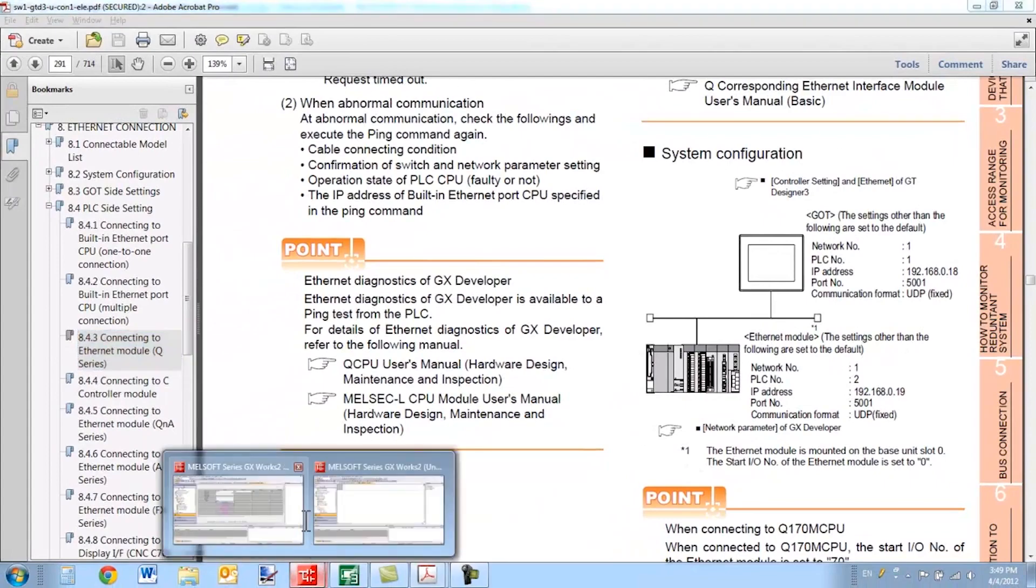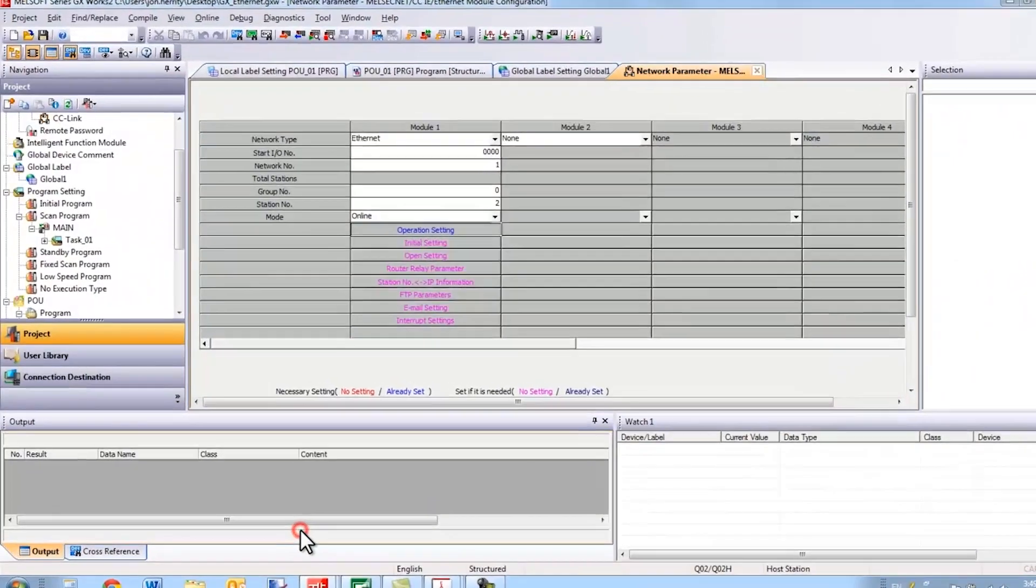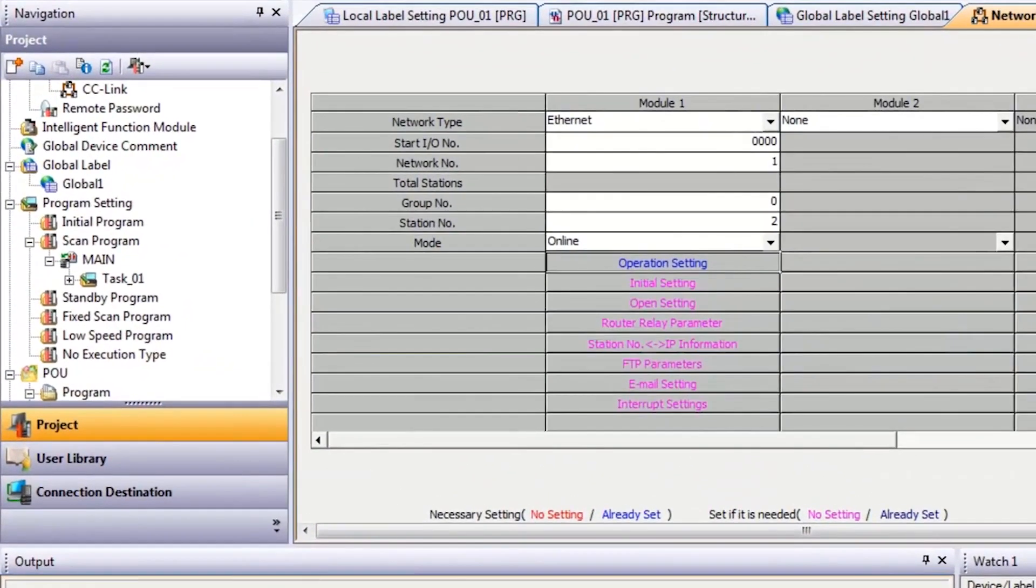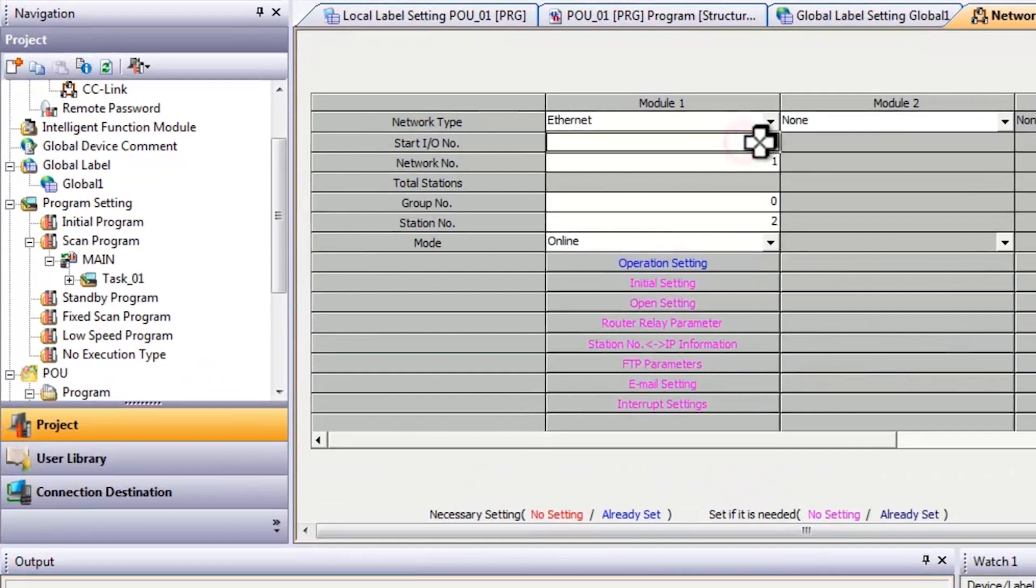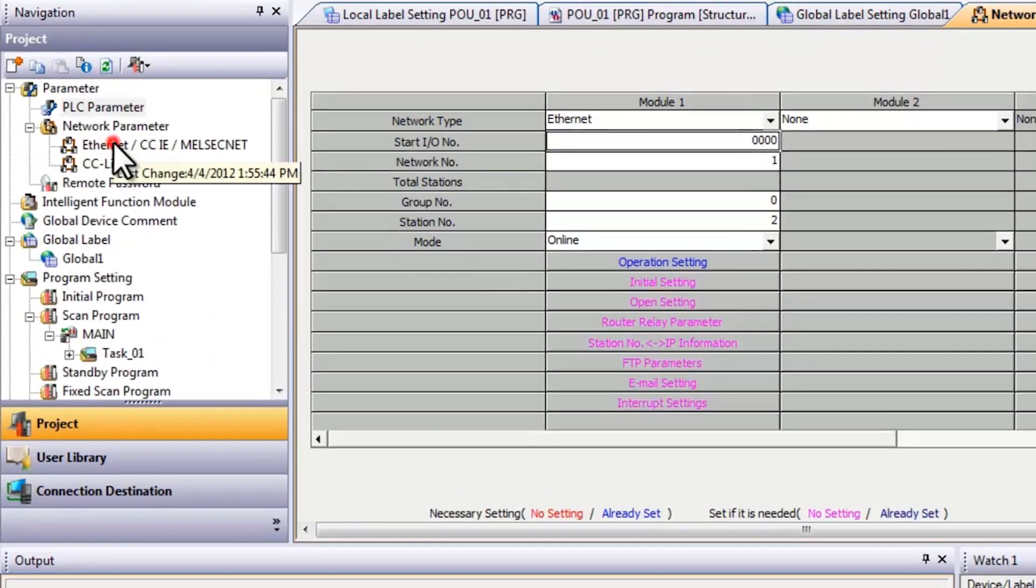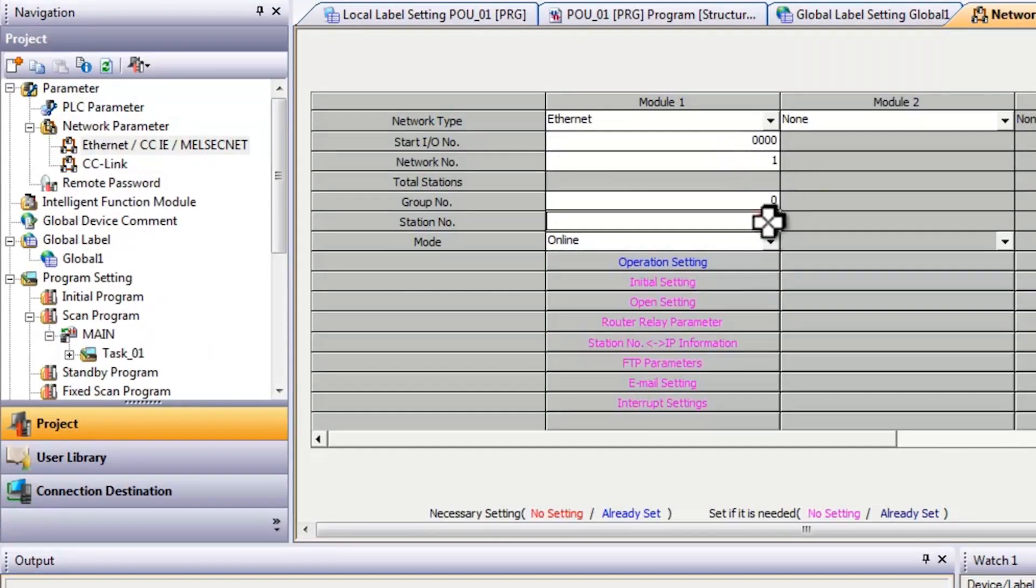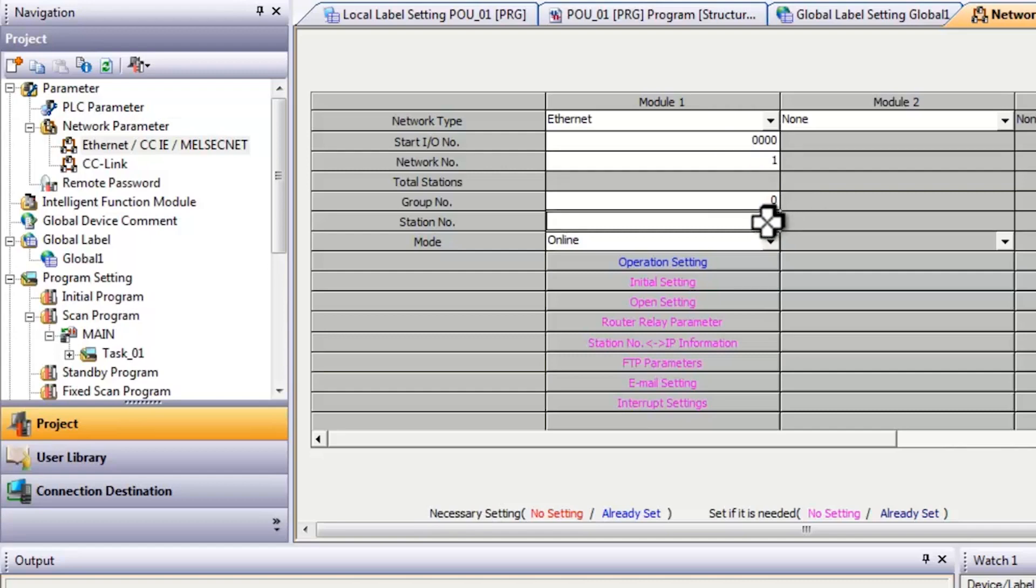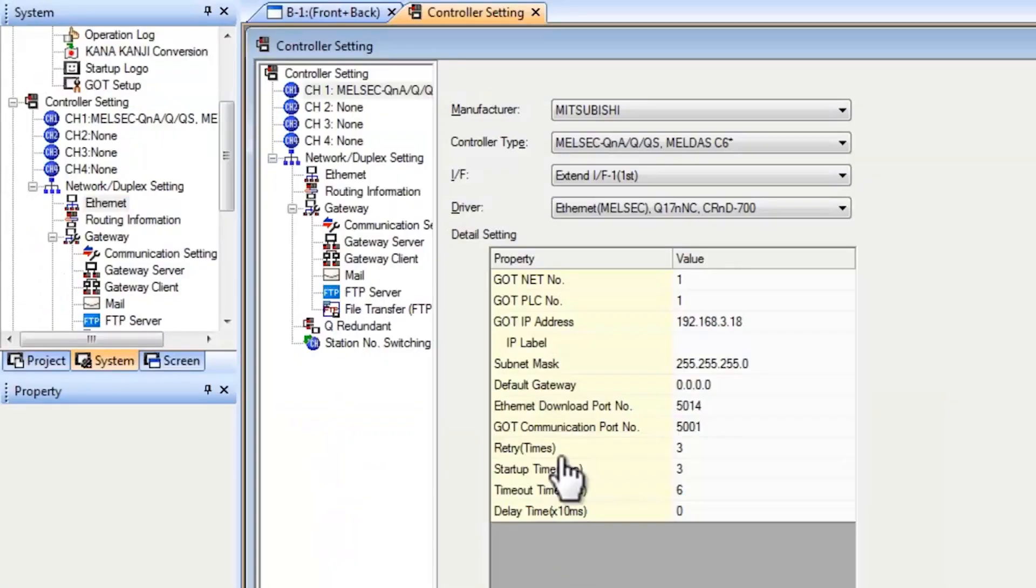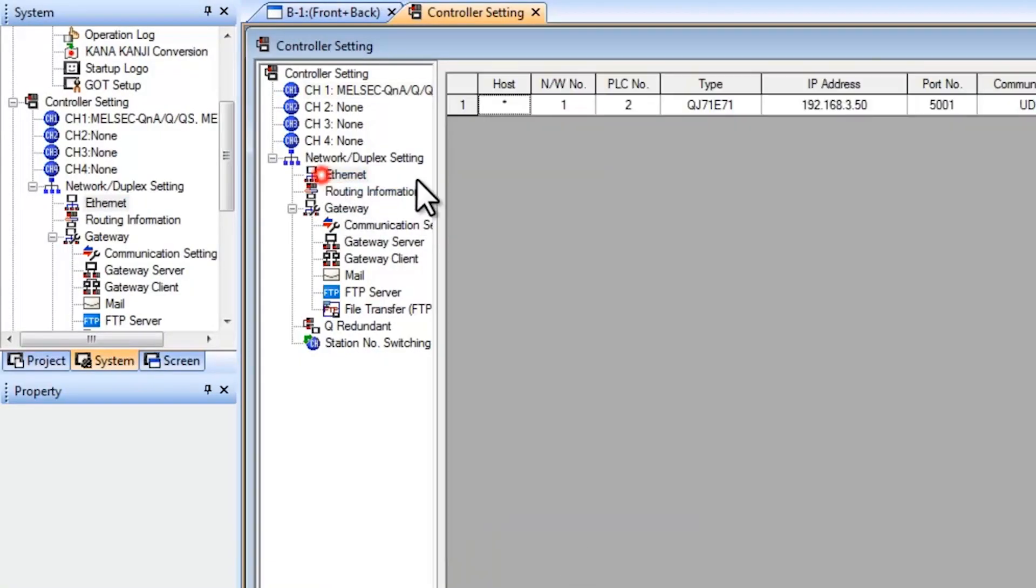And on the PLC side for the PLC program, for the Ethernet module, make sure your I.O. settings match your parameter settings. So again, in your Ethernet settings here, you would select your network numbers 1 and the station number. On the PLC side, it's known as the station number. It's not the PLC number, it's called station number. 2 needs to match the 2 for the PLC number on the GOT.